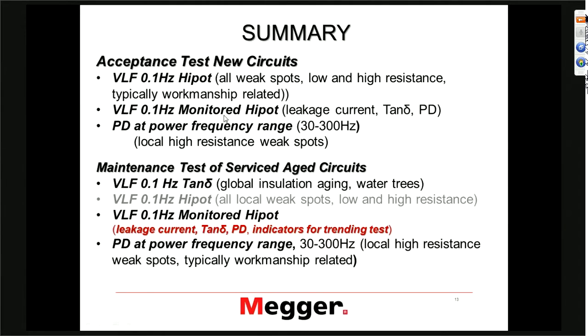As a summary: for acceptance tests of new circuits, we have 0.1 Hz VLF hypot testing which will find all major weak spots. We can do a VLF monitored hypot test using leakage current, Tan Delta, or PD. Tan Delta is a little questionable for acceptance tests. We can do partial discharge testing. To do it in one test, if you do a monitored hypot test where you use PD as a monitoring level, that is a very pragmatic approach.